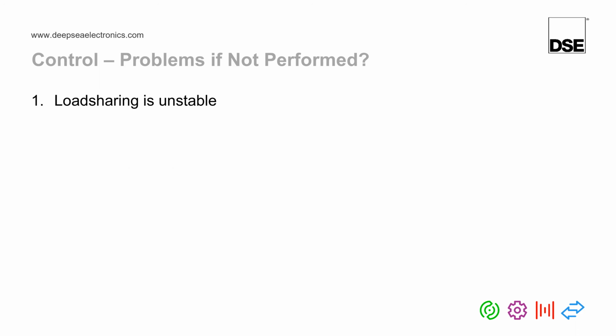as it says there, unstable load sharing. But as we're also using the governor and AVR for synchronizing, if you're having unstable, erratic, or long synchronizing times, this also suggests that you have very bad switch 1 and switch 2 settings, or no control over the governor or AVR itself.